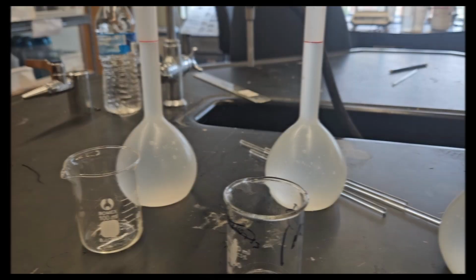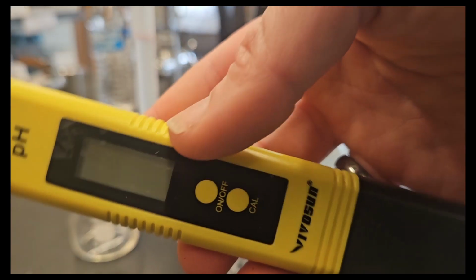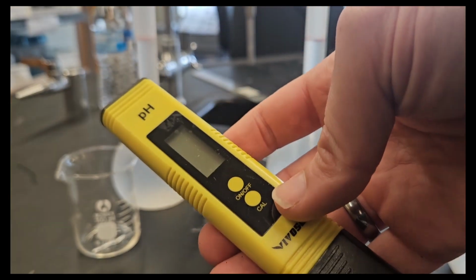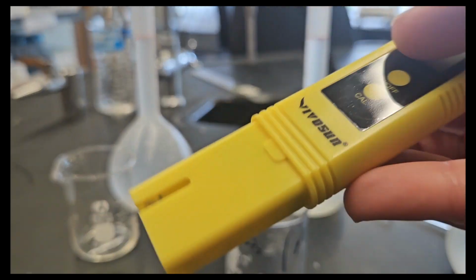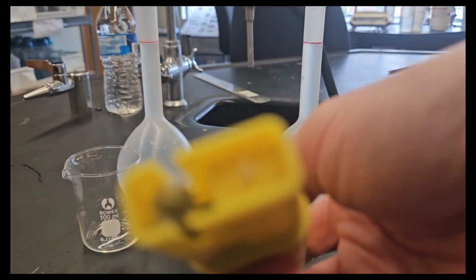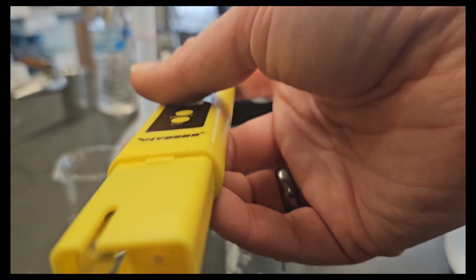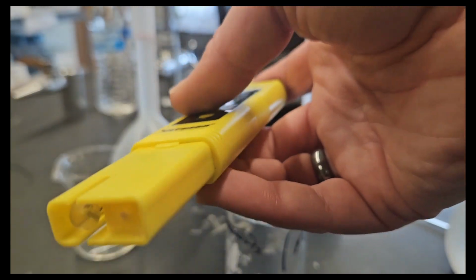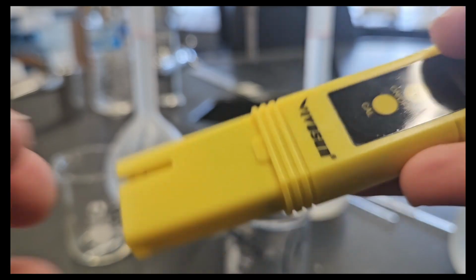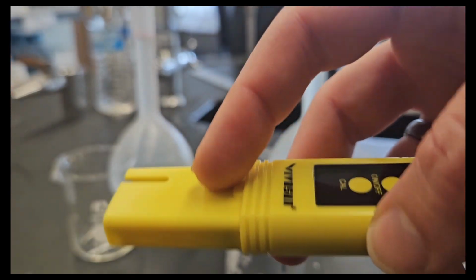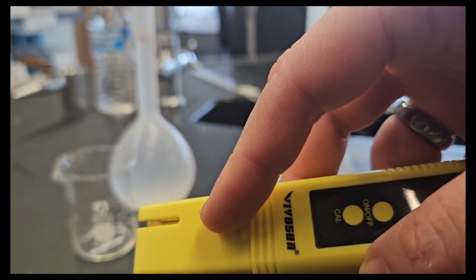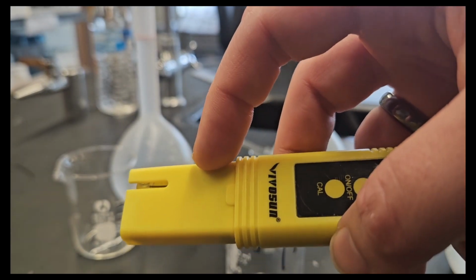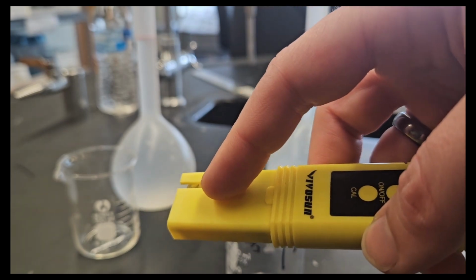Okay, first thing we should note is our pH meter. Notice it has an on-off switch and a calibration switch. We have the glass bulb in there. That's the working electrode. The reference electrode is stored inside. When we dip this in, the immersion line is somewhere about halfway between here and here, so don't go past here. As long as we're fully dipping that, we should be fine.